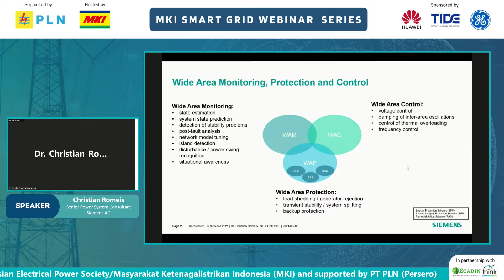So you might close the loop from the monitoring system, using PMU data, to incorporate it into control, perhaps into an HVDC control system, a thyristor controlled series capacitor system, or an SVC system, to control or damp these inter-area oscillations. Also, in cases of long-term voltage problems, you can start controlling actions such as switching capacitor banks based on wide area monitoring results, and then introduce protection schemes if the voltage continues dropping.